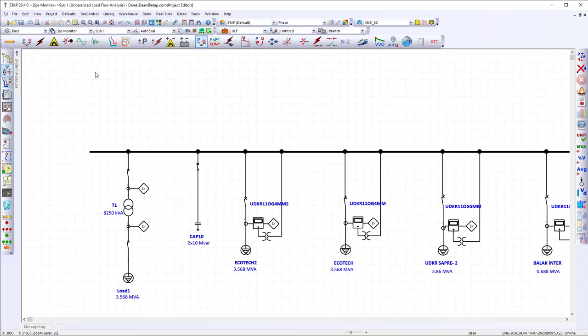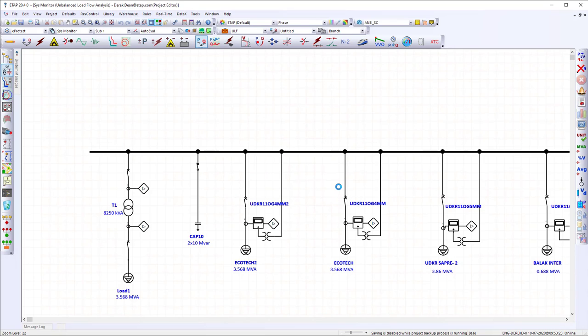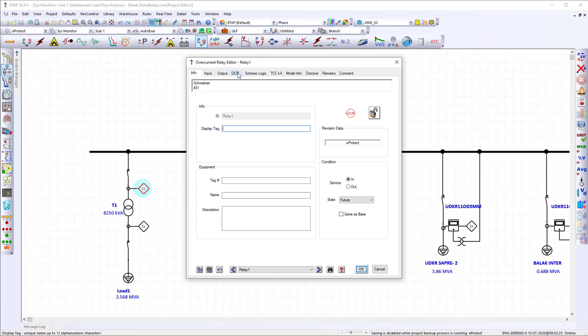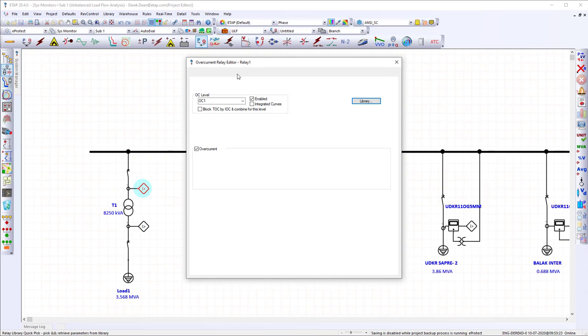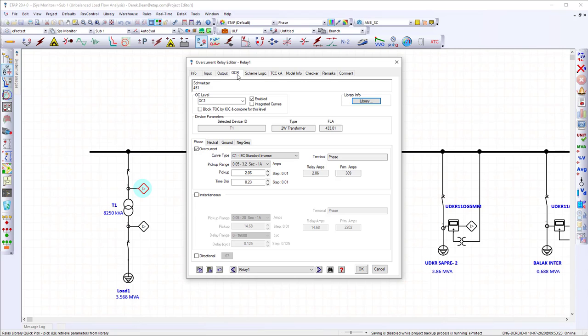The ETAP model is automatically updated. However, this data is sent to an eProtect revision, not the base revision, so you do not overwrite your base conditions. Relay 1 shows the updated pickup and time dial for this revision, 2.06 and 0.23.